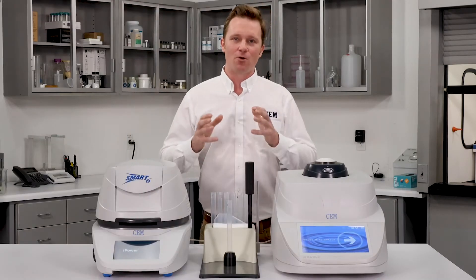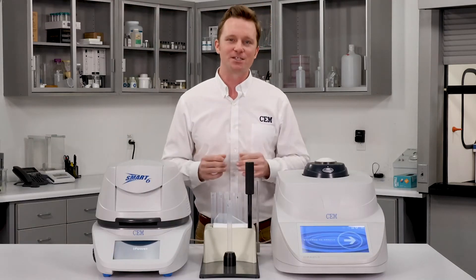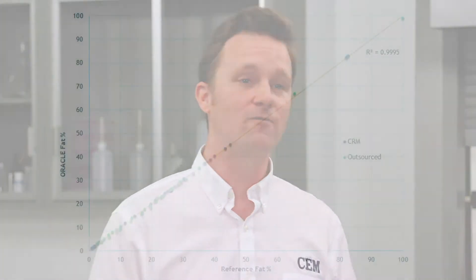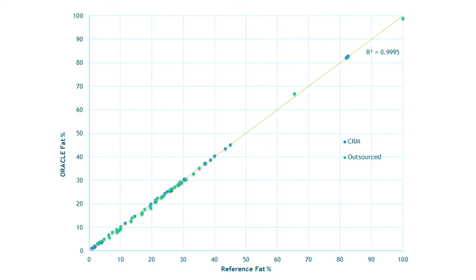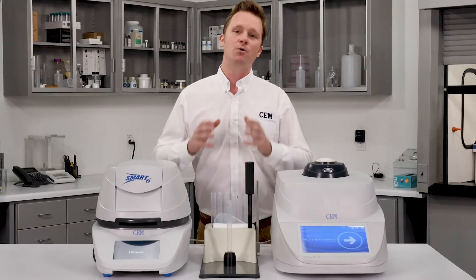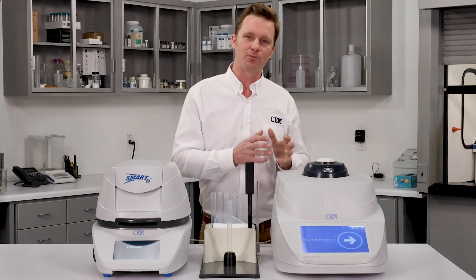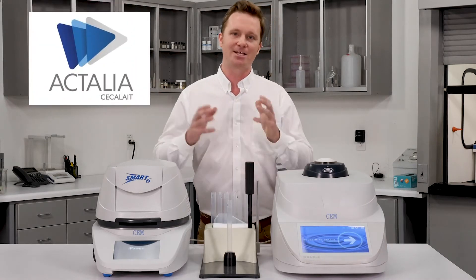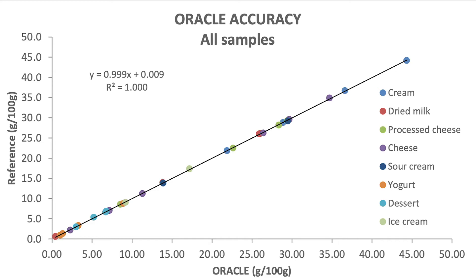During the development phase of the Oracle, we put it through the most rigorous validation process possible. We sourced countless certified reference materials and gathered samples from all over the world, sending them to accredited third-party labs for analysis. We compared those results to the Oracle and found perfect agreement — whether it was zero or 100% fat or any sample type in between, the Oracle matched standard reference chemistry results perfectly. We then sent the Oracle to the third-party accredited laboratory Actalia, and they determined that the Oracle was as reproducible and as accurate as reference chemistry.